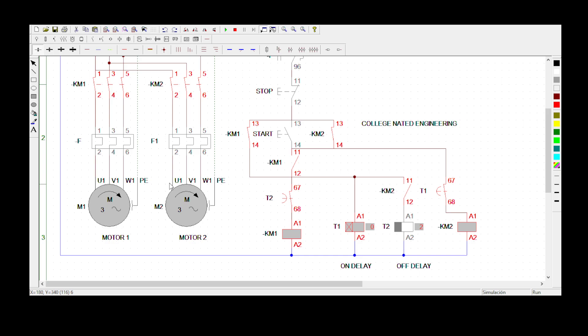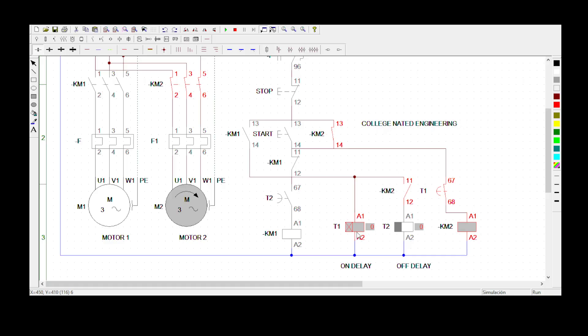Both motors are now rotating, but after 10 seconds we want only Motor 1 to stop rotating. Timer 2's normally closed contact must become normally open to stop Motor 1. The delay-on timer must always remain energized — because if it becomes de-energized, its contact becomes normally open and KM2 can no longer run. Immediately when KM2 becomes energized, that normally open closes so power flows and keeps Timer 1 energized. Timer 1 is actually receiving power from KM2 now.